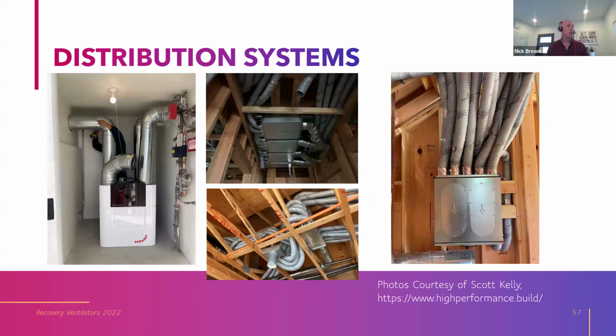And here are some pictures. On the left is a high-end install in a mechanical closet. They're using sheet metal ducts to get it out of that mechanical closet and into the OEM's distribution system. You can see each of those chassis allows you to hook up to the sheet metal duct from the mechanical room, and then multiple 4-inch ducts are affixed to that chassis that takes the air around the house, both exhaust and supply.